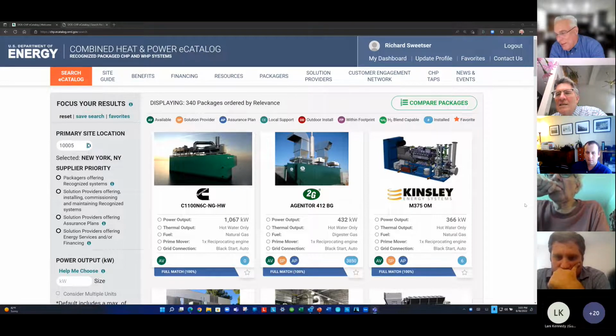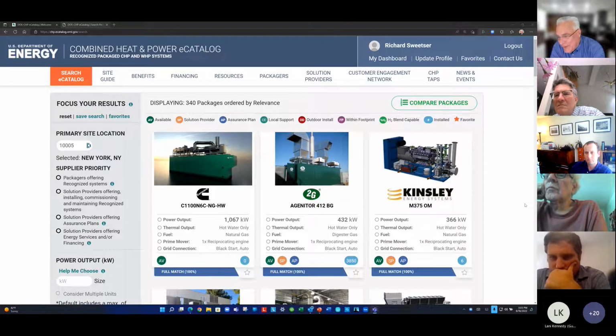Interesting, and also, by the way, the peaker turbines, if you're on an industrial site that still uses the heat, it depends. If the signal goes out and it's worthwhile, the industrial facility would drop down the power requirements and likely still needs the thermal. In the case of a place like Princeton, although Princeton is changing a lot, Princeton has a 15 megawatt CHP plant, but they only run it at 8 megawatts. They've got 15 megawatts they can go up to, and they have steam turbine chillers and a steam loop in the system for now. So there's all sorts of cases. The answer is it depends.